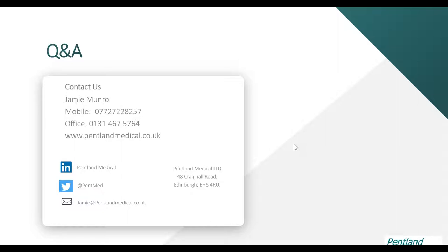Do I still have to observe IV infusions, or can I trust the Monidrop device? You can set the alarms and alarm limits for the device, and it will alarm when it goes outside those parameters. However, even if you haven't set any alarm limits, the Monidrop will always alarm for occlusion in the administration line or IV cannula - and it does this a little earlier than you might expect.